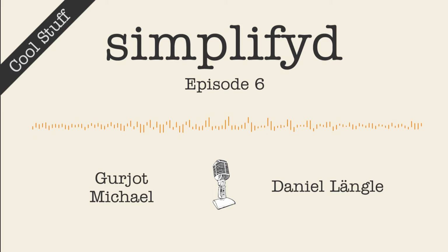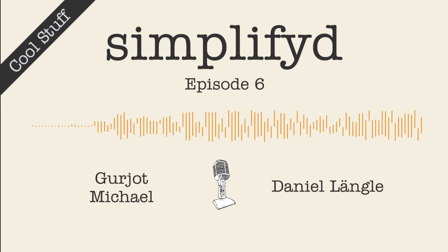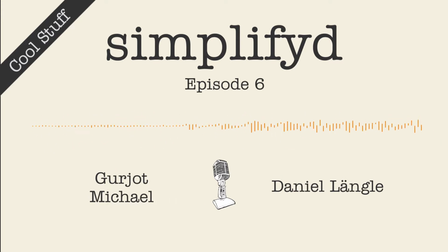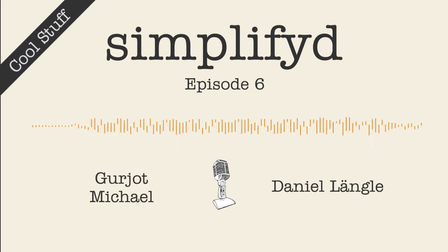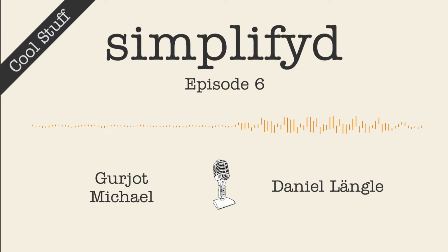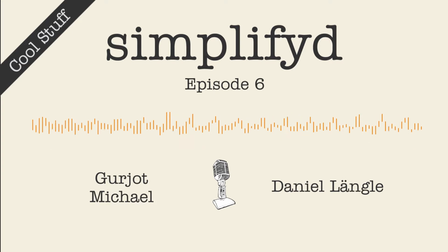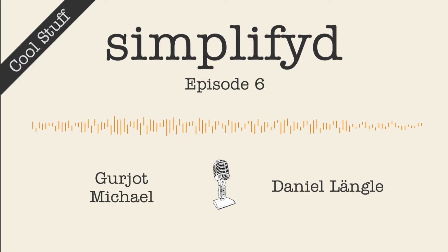Exactly. It's like imagine you have a long hose and you stand on the end, but it's a very flexible hose, so it builds up the pressure, and then when you feel the pressure reach the limit, you sound the alarm. And so what you want is to put this level as low as possible to have the alarm as quickly as possible in those old devices. But when you put it as low as possible, if the patient shakes the arm, for example, and there is a pressure change, it'll start beeping. Exactly. The alarm is triggered as well. So that's why those pumps beep very much.